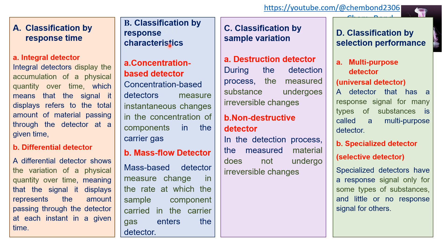Classification by response characteristic gives two categories: concentration-based detector and mass flow detector. A concentration-based detector measures instantaneous changes in the concentration of the component in the carrier gas, meaning the signal is related to the concentration of the solute. A mass flow detector measures the change in the rate at which the solute component is carried by the carrier gas, so the signal is related to the rate at which solute material enters the detector.